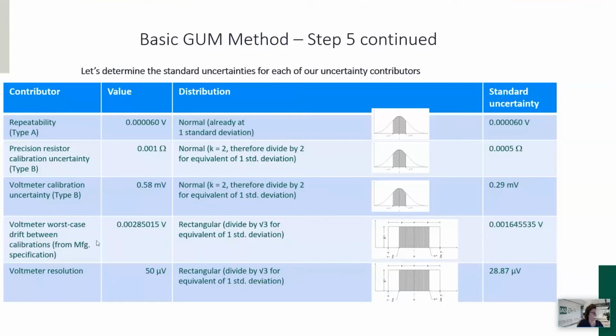We have the voltmeter, and we decided we're going to use the specs as a worst case drift between calibrations. So we need to divide. We assign a rectangular distribution, and the reason we do that is because we know nothing about how they came up with these specs. It's just a number. If you look at this rectangle here, the vertical portion is the probability of where a value might fall. We don't know anything. All we know is it's somewhere in between these outer limits.